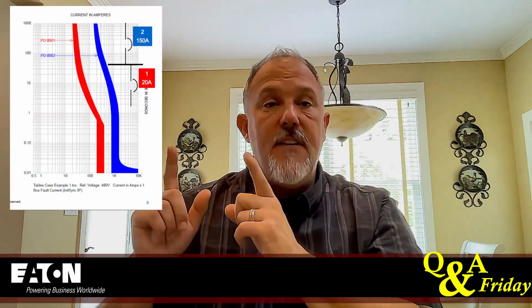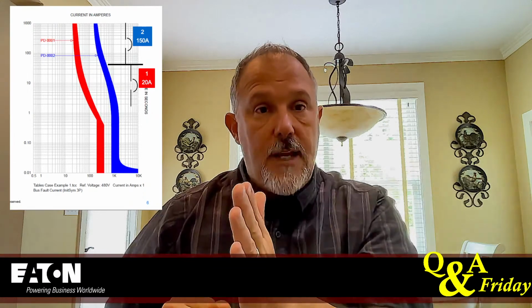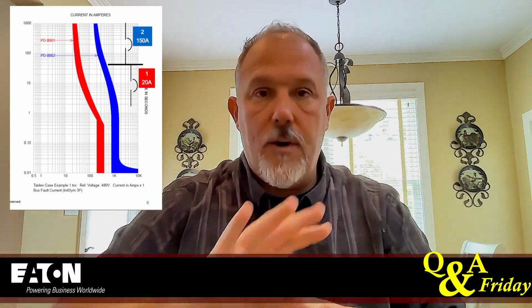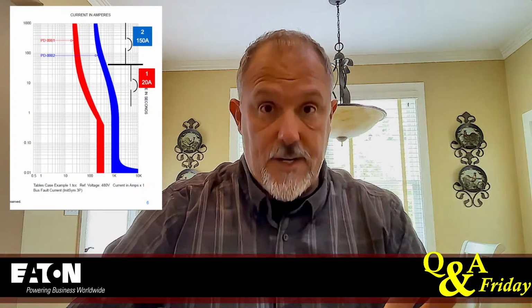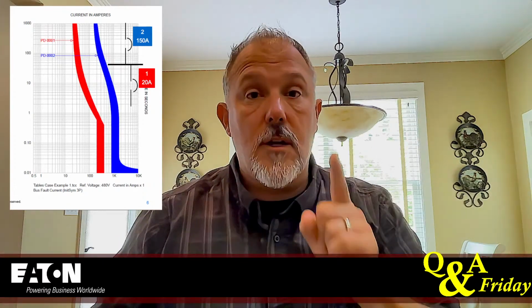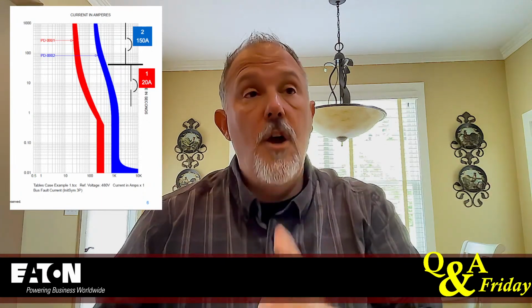If that red curve encroached in and overlapped with the blue curve in that long time, short time, long time delay region, it will not selectively coordinate. It won't even coordinate to 0.1 seconds. You just can't use the tables and leave everything else alone. You've got to plot the curves, unless you're using fuses. Fuses, you maintain a 2-to-1 ratio. You don't have to plot the curves.